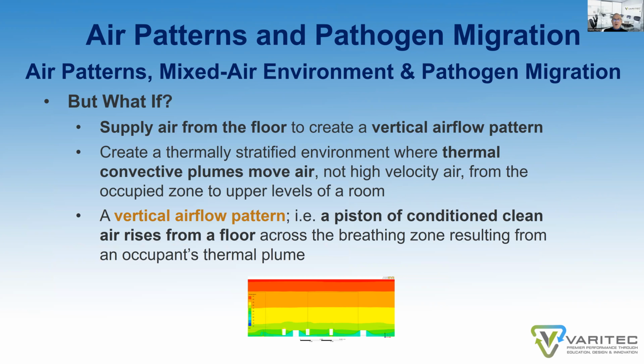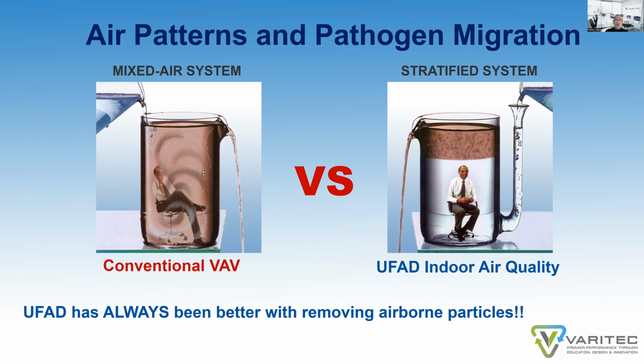But what if air, instead of being injected into the space at high velocity from ceiling diffusers, were supplied from the floor to create a vertical airflow pattern? What if a thermally stratified environment is created in a space and convective thermal plumes or heat plumes within the space actually move the air in the room and not fan energy? What would happen to contaminants and the risk of infection if a vertical airflow pattern was adopted, whereby a piston of conditioned clean air rises from the floor across the breathing zone and is evacuated from the space through return and exhaust grills mounted in the upper levels of a room? To give you a visual of what this could mean, Airfixture provided us with this rather compelling graphic. I think it's excellent to show you the overall conceptual differential. Well, this looks wonderful conceptually, but is it actually effective?